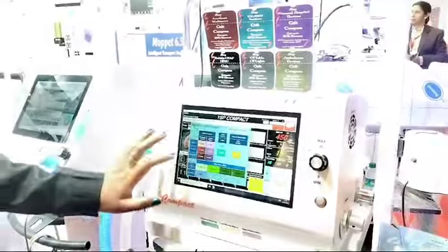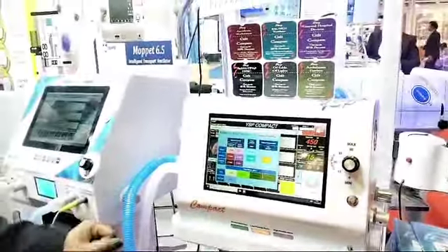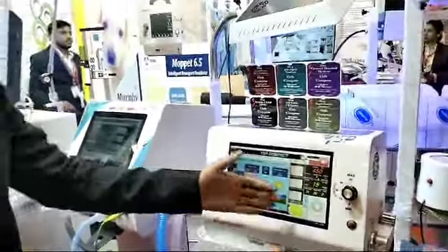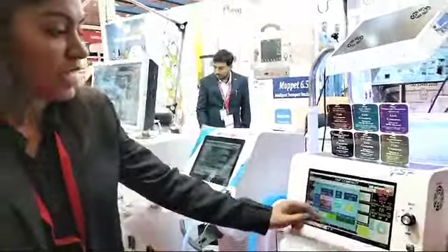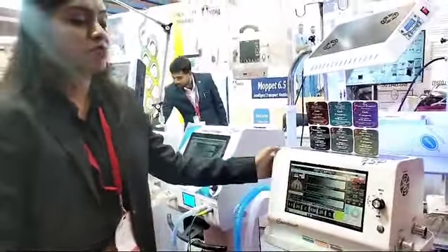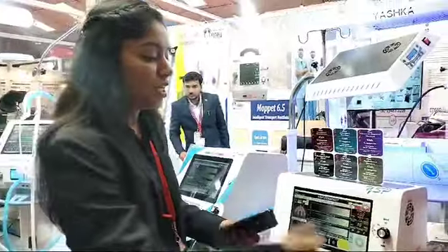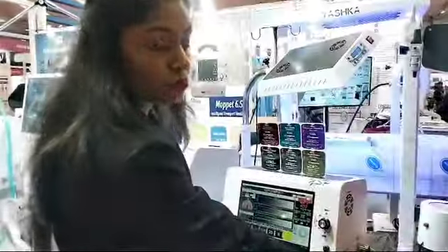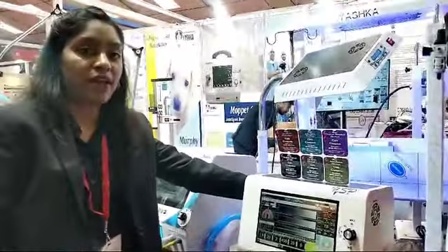Click on adult and you will get all the modes, clinical modes, machine control, dual control, patient control and all the NIV modes. This is turbine based ventilator, where you will be able to blend the oxygen with this knob. We are having oxygen port at the back.